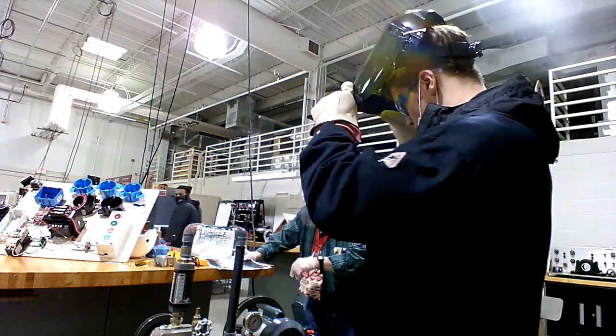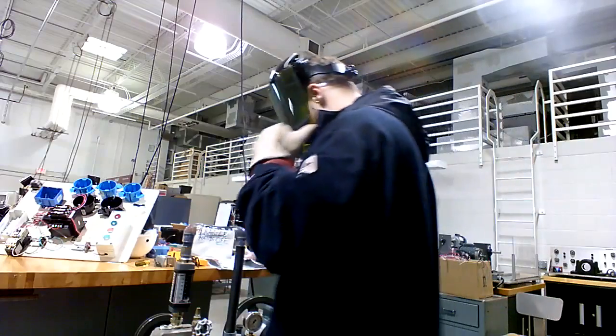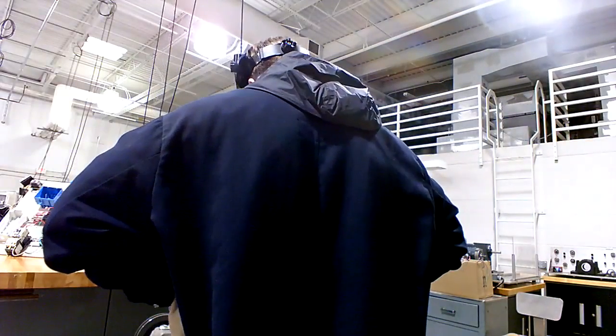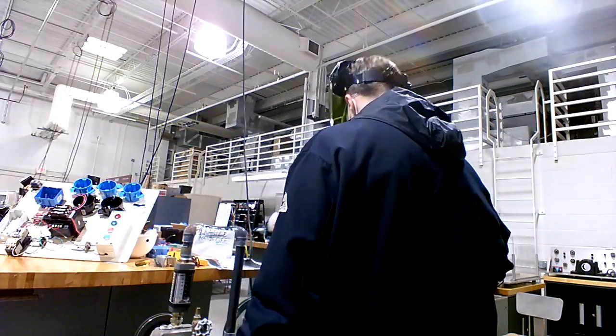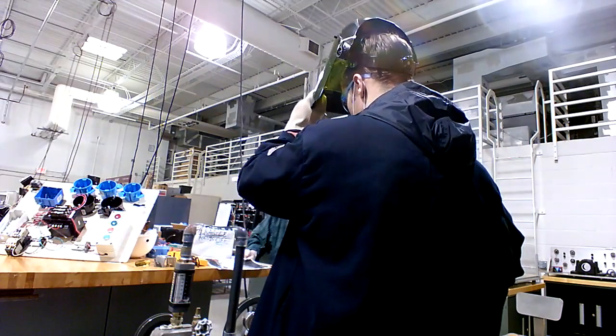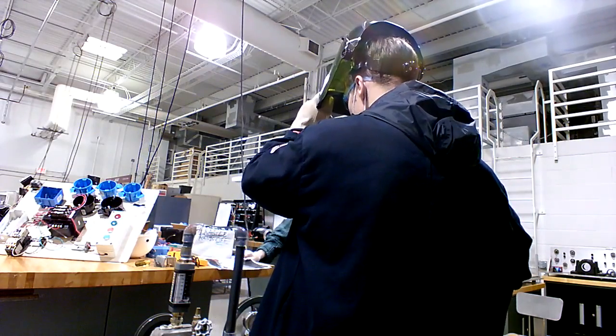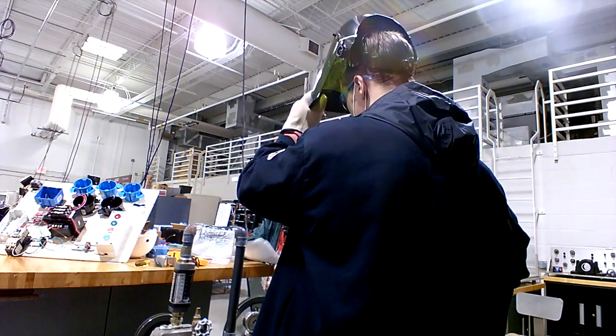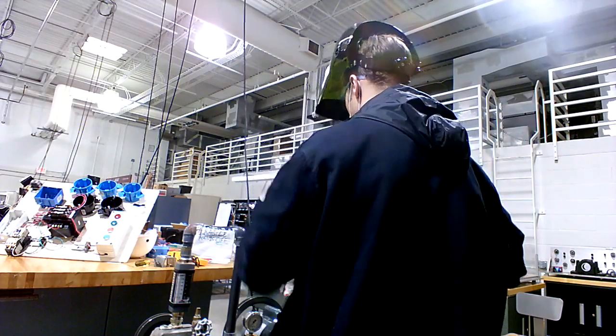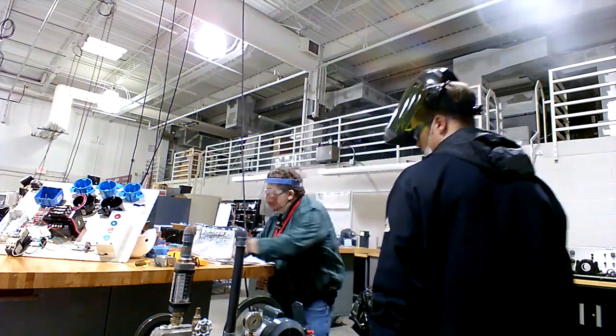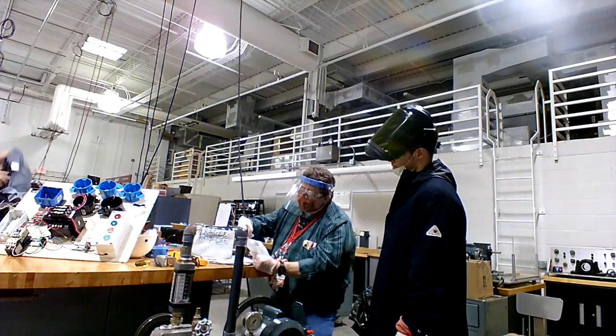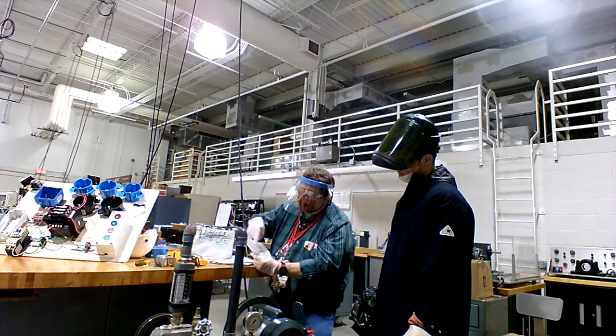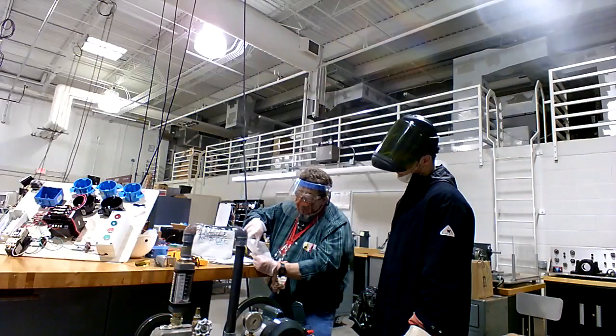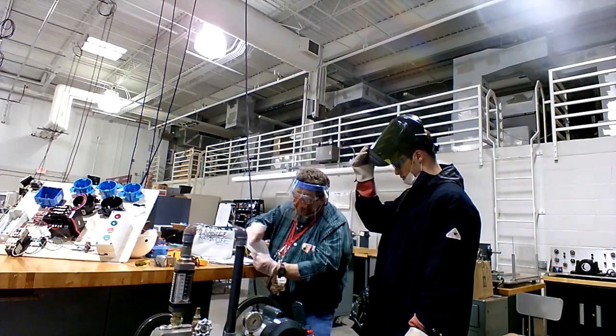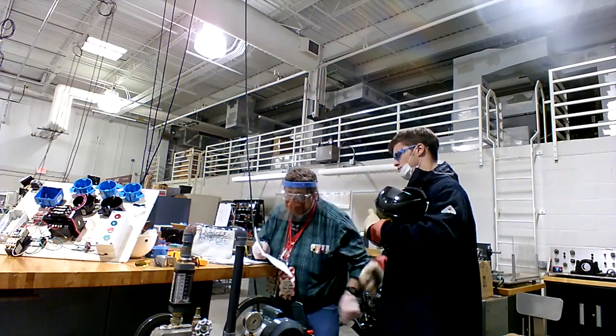Okay, now watch. This time we're going that way, so we'll push the switch on the front, right back off, and watch the foot. See it? It's going this way now. So whether it's a pump that needs to go that direction, or a fan, or a conveyor, that's what makes it go the other way. It's not changing the incoming wire, but it's changing the start wire. The outer wires will be the black and the red. You're changing those out here, the bundle, without changing the orientation of your main wire.